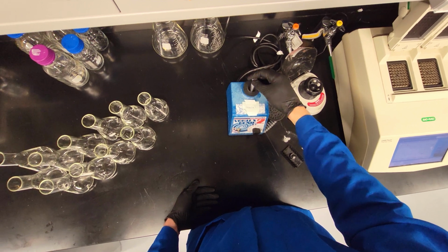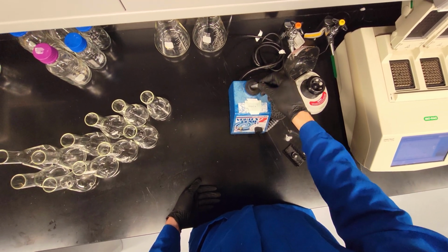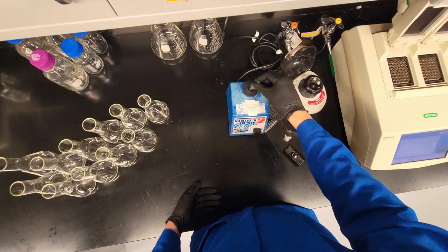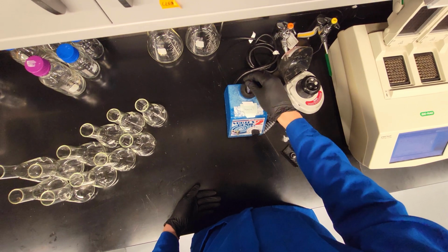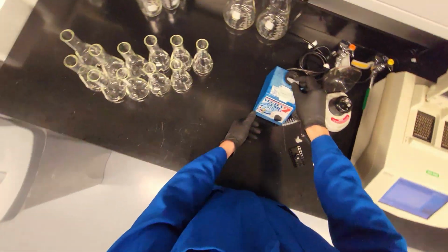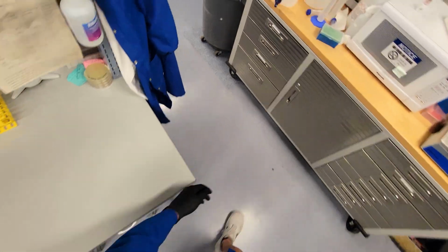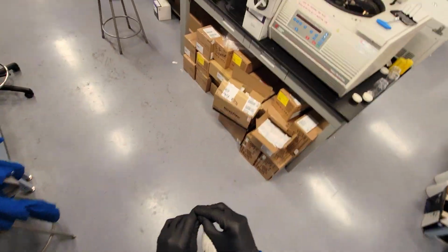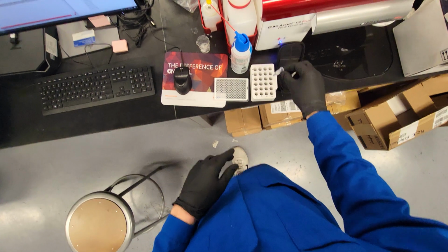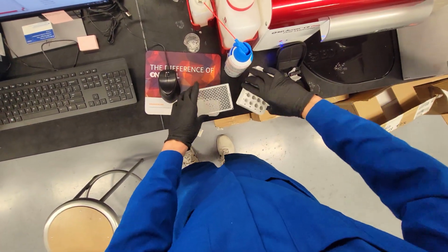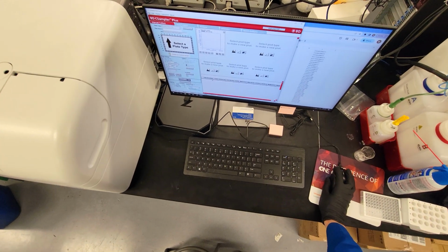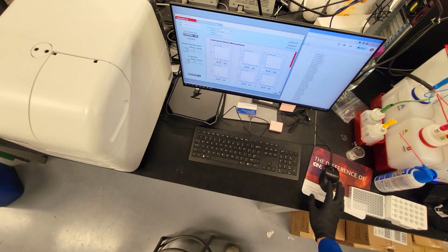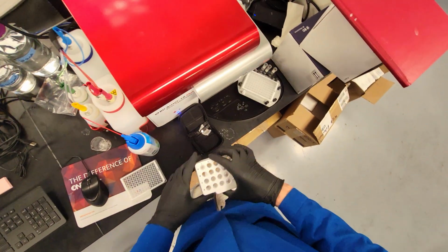Again, we need to run our quality control with the 533 nanometer filter, so that's already in the machine. And then once the QC is done, we'll switch it to the 510 nanometer filter so that we can measure GFP. So we'll put this in the A1 slot of this little, what is this, 6x4, 24 well plate. All right, so the flow cytometer is ready. We'll eject the plate and open the instrument QC panel, and we'll put this 24 well plate in.